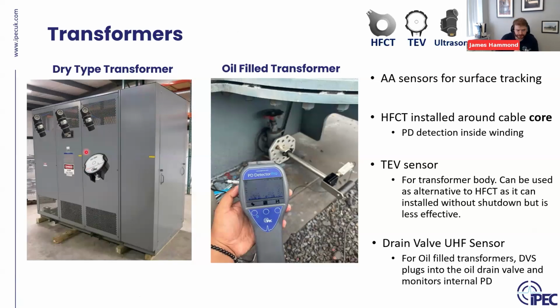And then in oil filled transformers on the higher voltages, in transmission level, often where there is hopefully DGA going on, or some type of testing anyway, but we can get right inside the oil itself using a drain valve sensor, and you can detect PD that way as well.